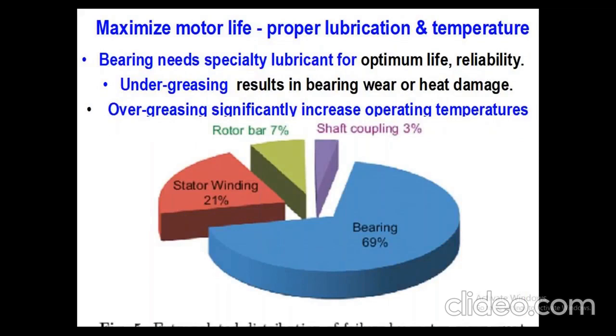Bearing failure is due to repeated pumping of multi-purpose grease in textile mills. On high capacity motors, I am talking about the ring frame motor, we have seen in some textile mills that every month they pump more and more grease. You will be surprised: when you go to the audit, when the machine is stopped and taken for maintenance, the maintenance person greases the ring frame, and when he switches it on, the ring frame trips 3 or 4 times due to over greasing. Over greasing makes the grease act as an overload for the machine, which is not good for the textile mill. So you have to monitor and pump the grease, and the grease has to be a specialty lubricant.